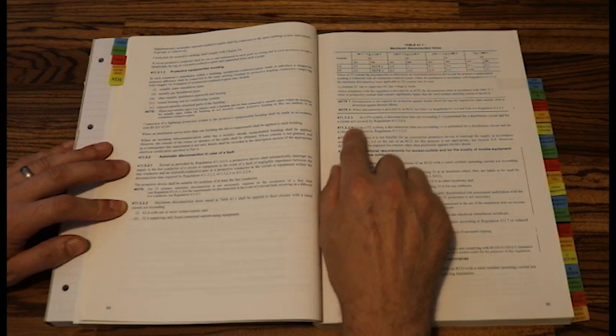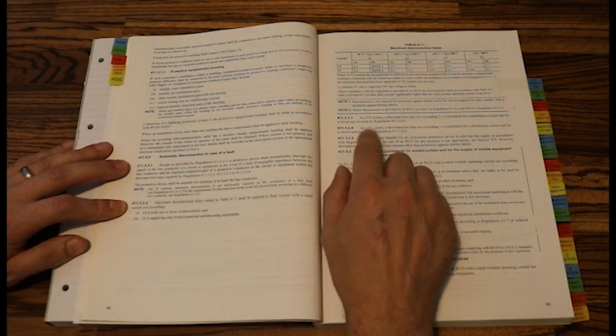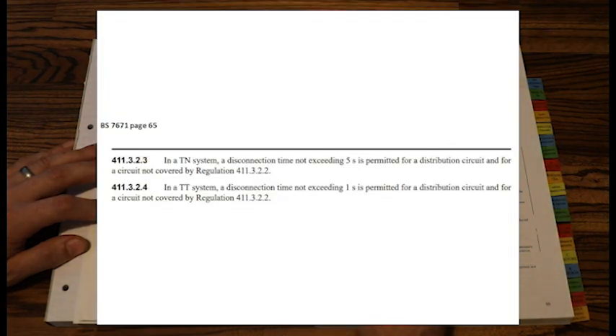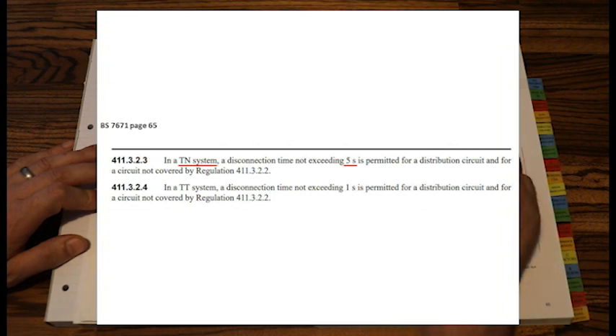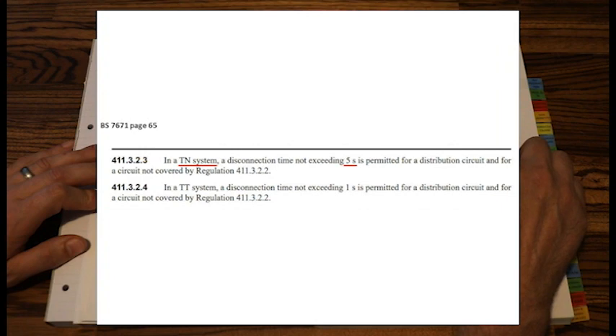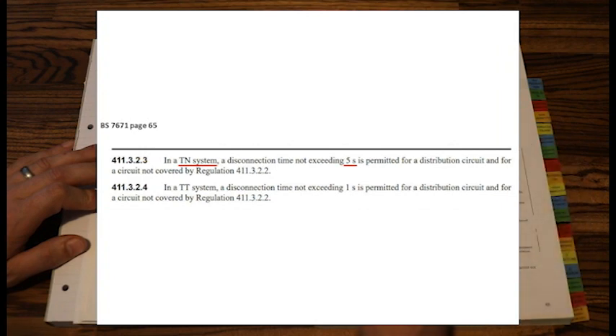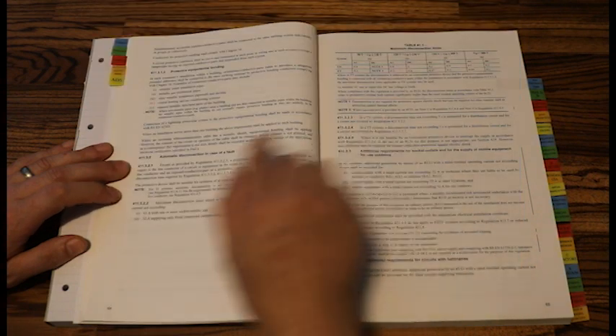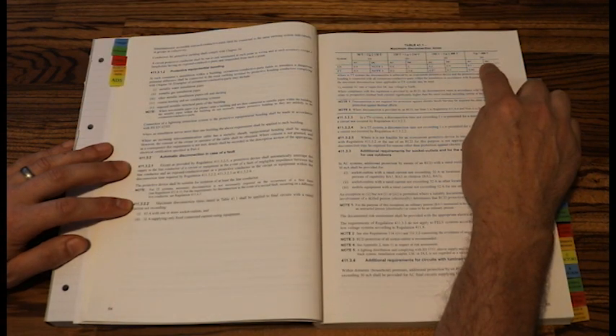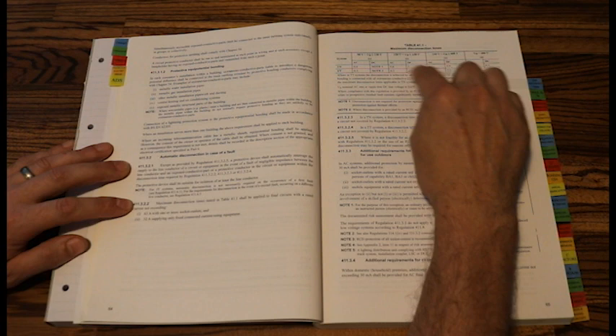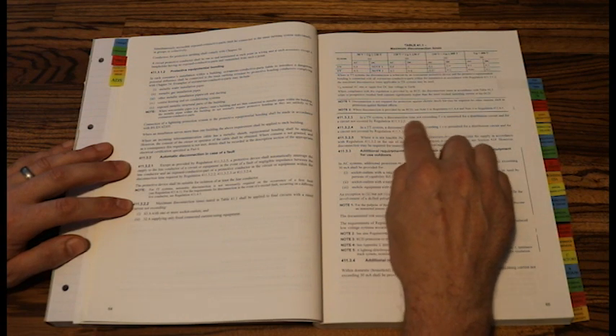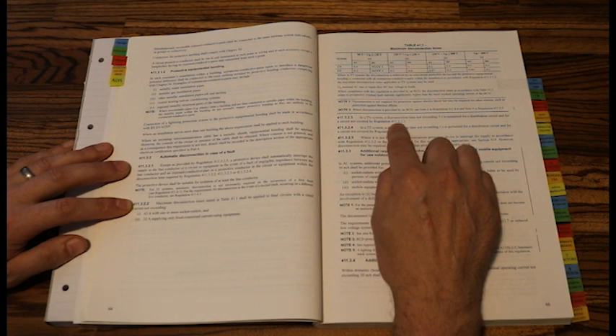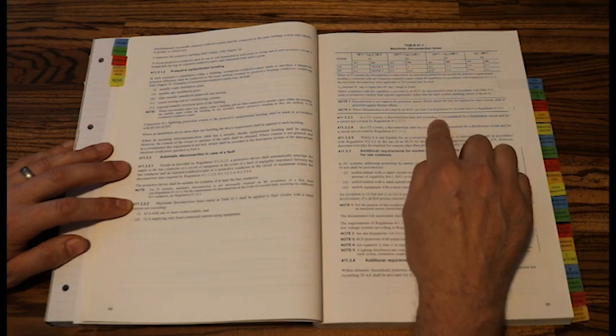Below it, we have 411.3.2.3 and .4. It says in a TN system and in a TT system. Our question is a TN system, so we're here. In a TN system, a disconnection time not exceeding 5 seconds is permitted for a distribution circuit or for a circuit not covered by regulation 411.3.2.2. So if my circuit is not covered by this table, I have this regulation. So my maximum disconnection time is 5 seconds.